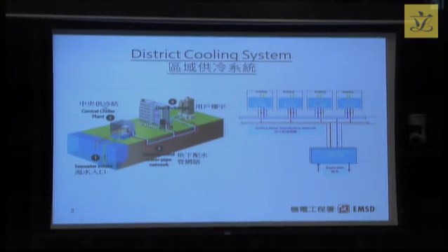This is a central cooling system, and its special characteristic is that we would be concentrating all the chiller plants at a central station. Through the use of sea water, we would provide chilled water, and we are able to achieve high efficiency. Then, through underground water pipes, we would be distributing or sending the chilled water to the different buildings.